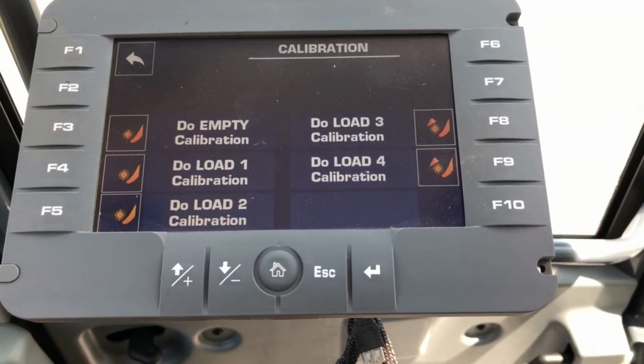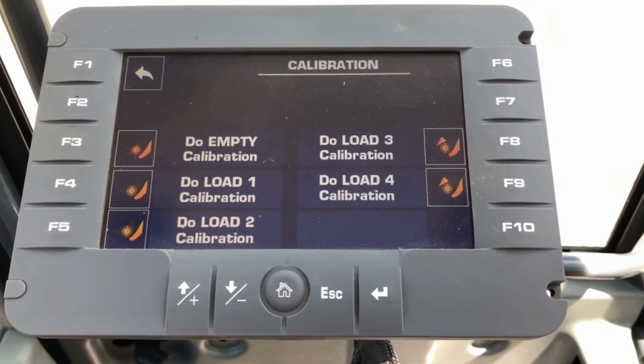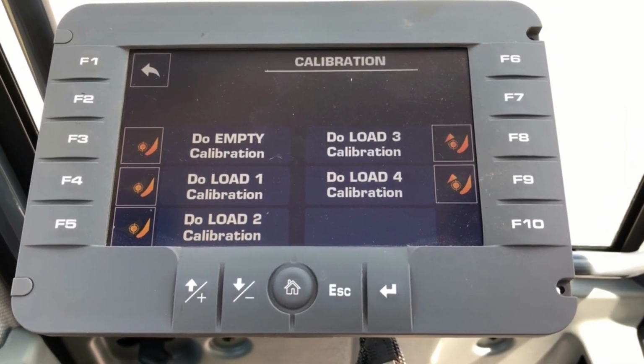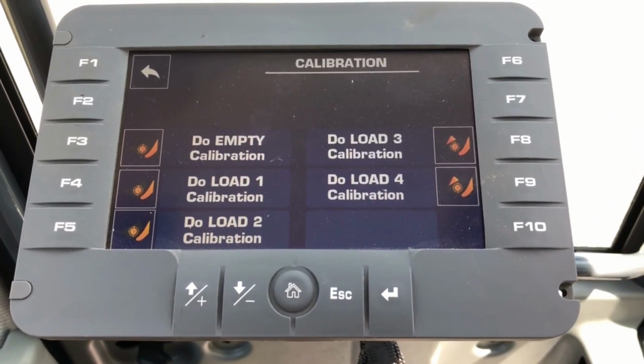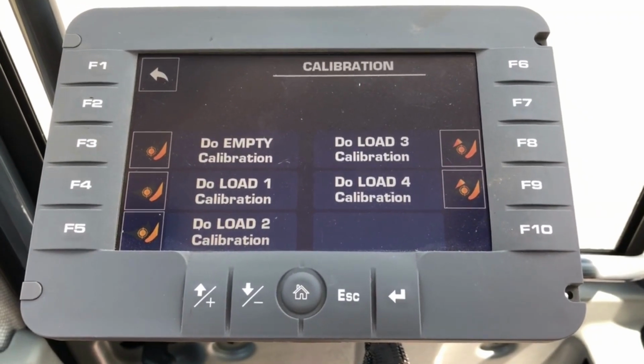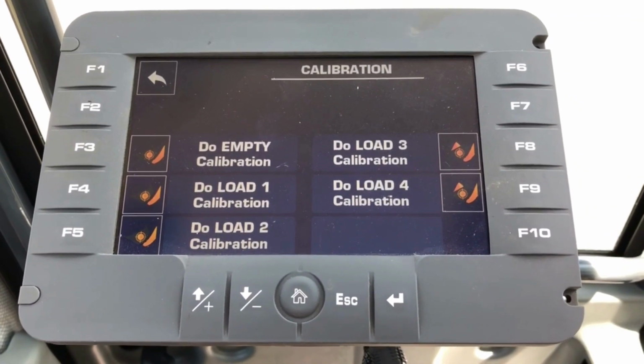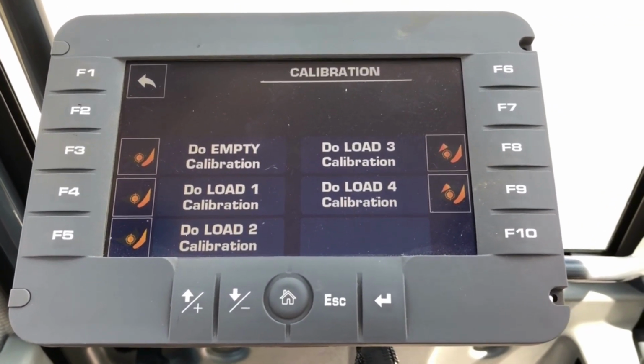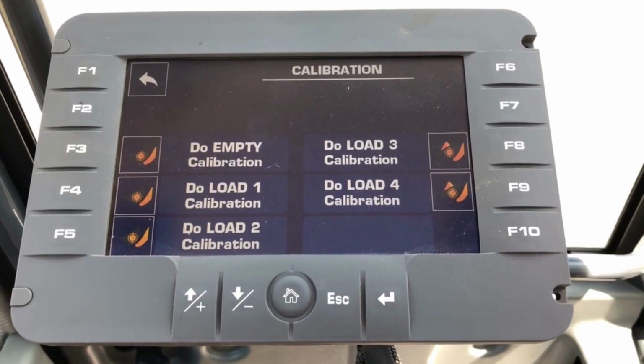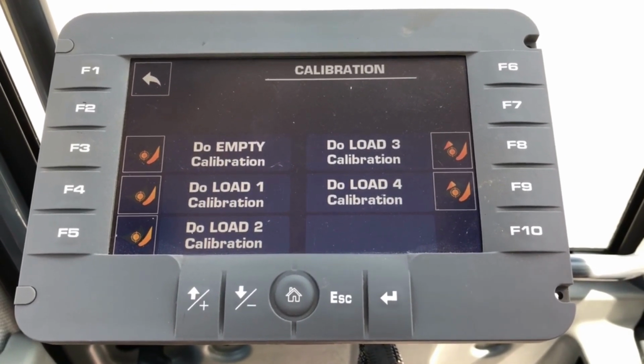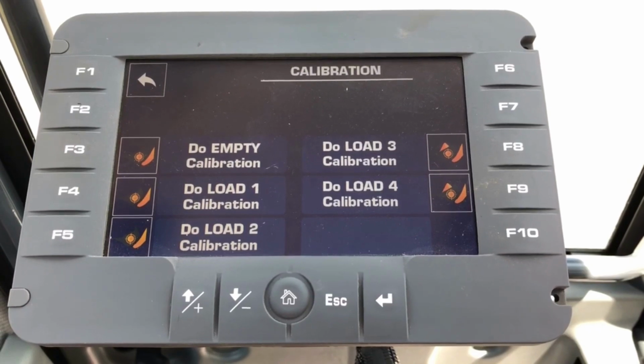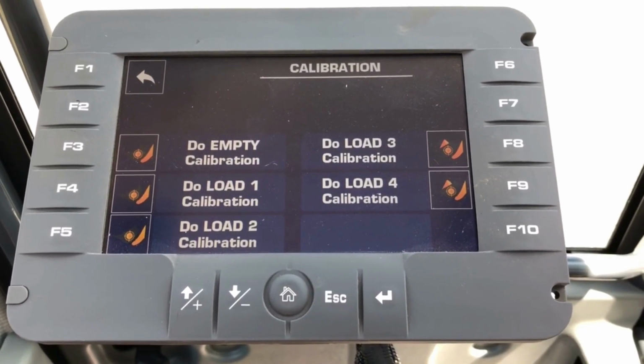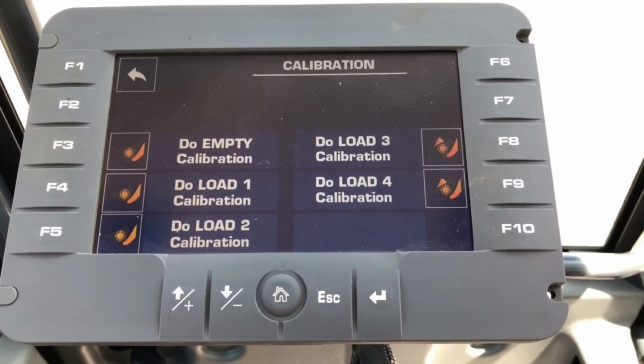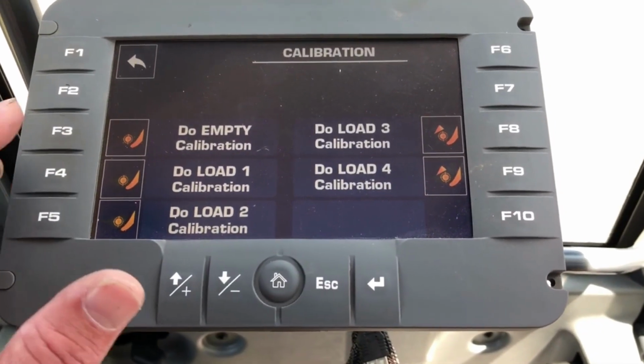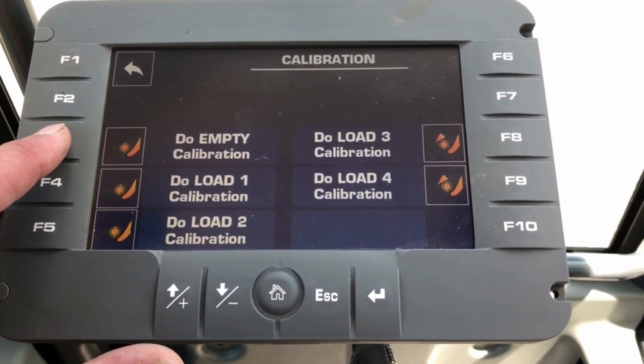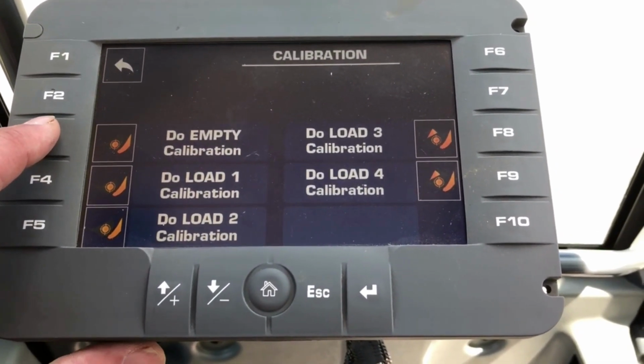You see it's going to come up to your different calibration points, your empty cal, your first load, your second load, your third load, and your fourth load. Your first load will be your lighter of the loads, then you want to increase gradually up to about a full bucket for load 4. You can start with do empty calibration, so hit F3.